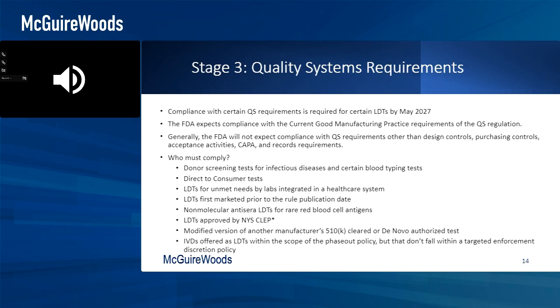And then once we get into the more complex tests, the LDTs approved by CLEP, compliance will be expected, generally speaking, as with any modified device that's currently on the market under a 510(k), and any IVD offered as an LDT within the scope of the phase-out policy that doesn't fall into the other targeted categories. It's kind of the catch-all other bucket. So effectively, the more complex your test and the higher risk of harm, the more of these quality system requirements you're going to have to comply with.